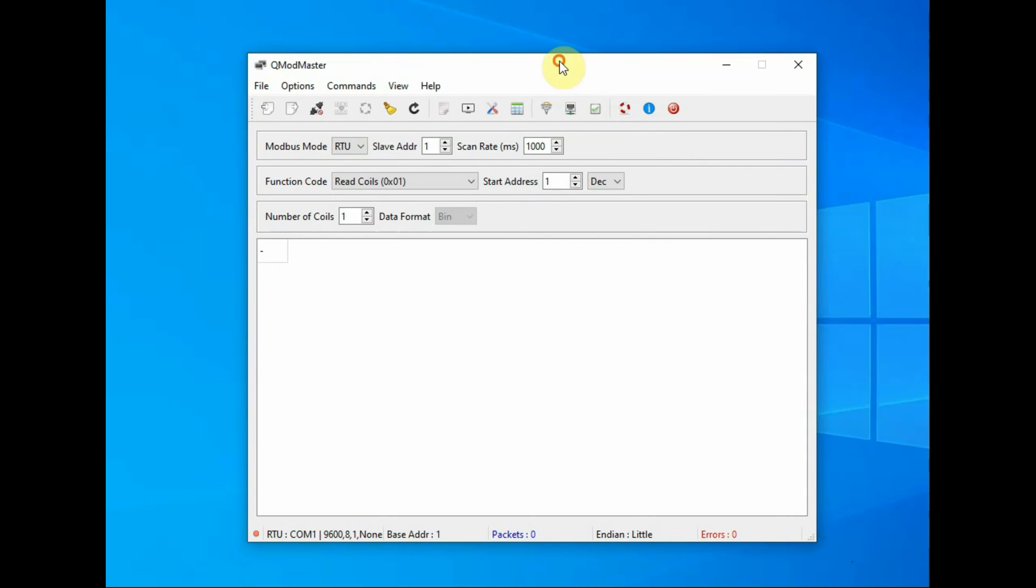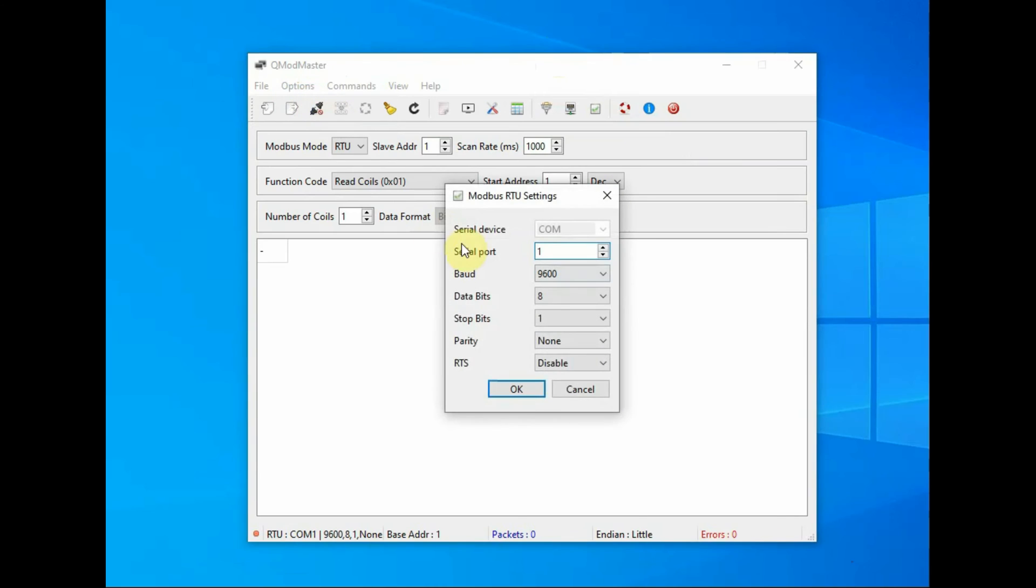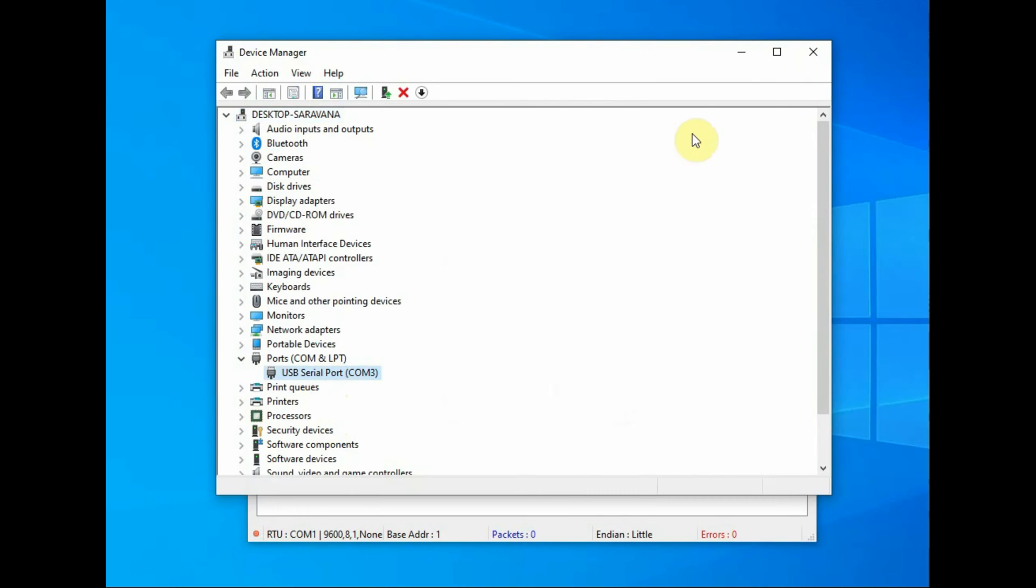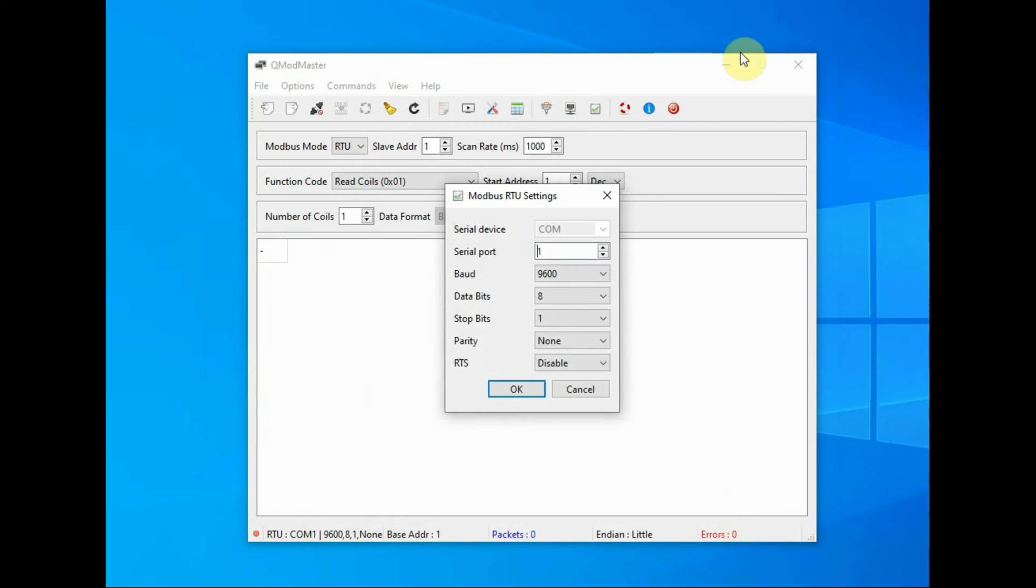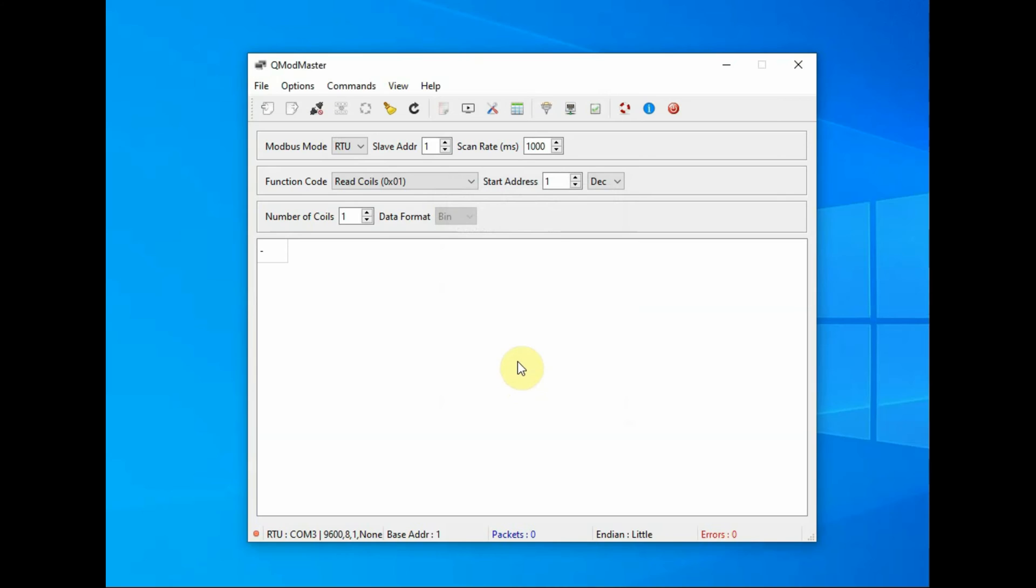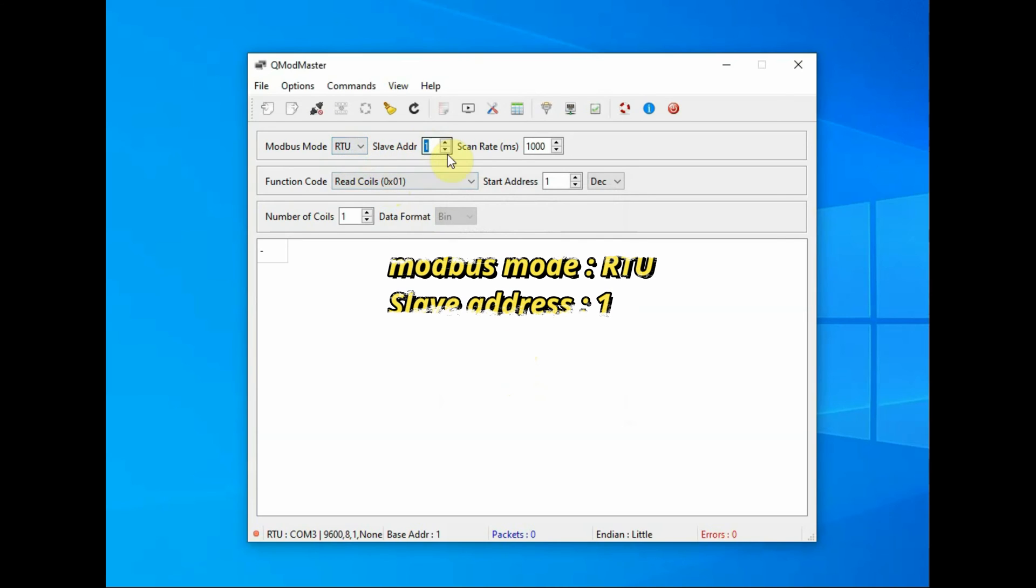Open QMod Master and then from options Modbus, select Modbus RTU and set the serial port, that is the serial port allotted to the USB to RS-485. Baud rate is 9600 and then Modbus mode is RTU.